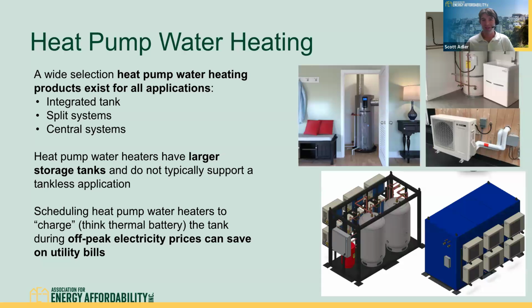The next one is a split heat pump water heater. This is the top right here, where it's pretty similar to that mini split. You've got that outdoor heat pump unit creating hot and cold refrigerant or directly hot and cold water for the SanCO2 system. And then you have kind of the indoor unit, which here is just a big storage tank, which is holding all your hot water. And then what's really common in multifamily is these central water heating plants, and there are alternatives for central heat pump water heating. This here is an example of a skidded product with the heat pumps on the outside and then with storage tanks on the inside.